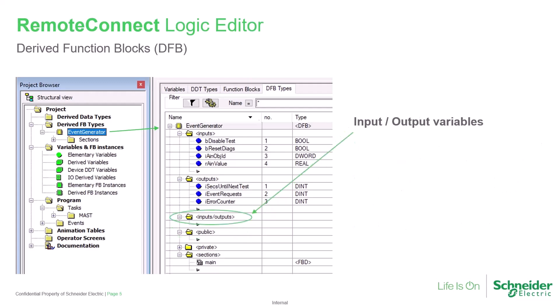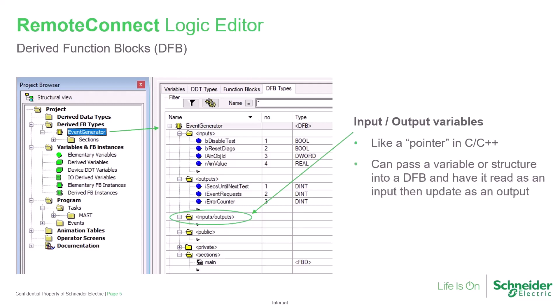A third type of DFB variable that can be configured is the input-output variable. This type may be used like a pointer in a C application. It allows passing a variable or a structure, such as an array, into the DFB to be read, and then allows updating the variable's value for use elsewhere in the application.